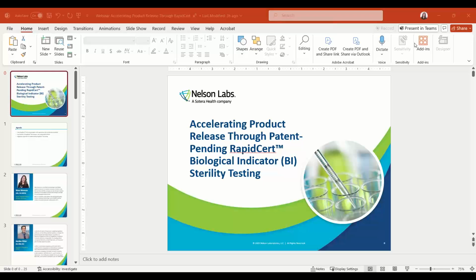We've also done validation work for a couple of our PCDs, so that's PCD 007 and 008. This is where the BI is in direct contact with the PCD material, the tubing and cap, so not contained within a glassine envelope. So we've validated that as well. So all of those should be able to be used with this RapidCert process.